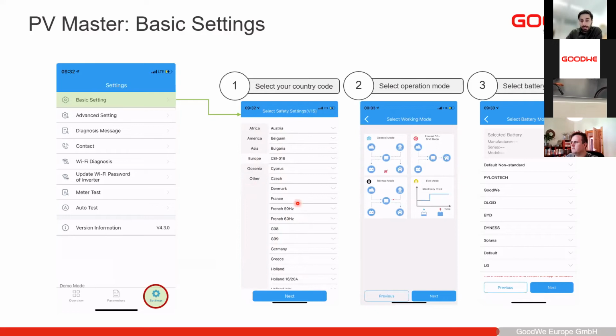So in this case, I'm located in Germany, so I would then click on Germany, and then after that, I need to select the work mode. Here we have a few different work modes. Usually it's only these 3 that we need to consider: the general mode, the backup mode, and economical mode. In maybe 90% of the cases, general mode will be the best one. This will optimize the self-use of the facility to optimize the PV generation and the battery generation. You do not need to do anything additionally.